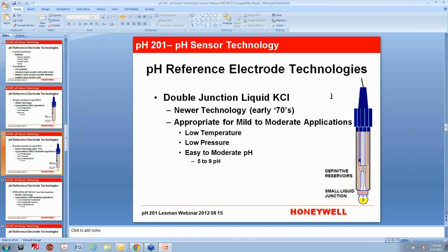So there are a lot of single junction and double junction sensors out on the market. This particular one is with a liquid, and I wouldn't recommend it beyond 5 to 9 pH. And folks, if I give you temperatures or pressures or pH ranges, those are just general guidelines. It's kind of a starting point. If you have some weird ionic species in your process or some chemicals, then the 5 to 9 pH or the 6 to 8 pH may not even be a good guideline, because it could attack and mix with your particular sensor technology.